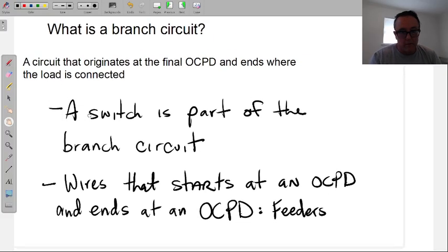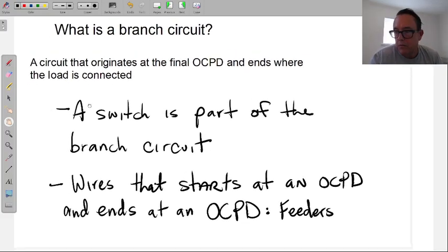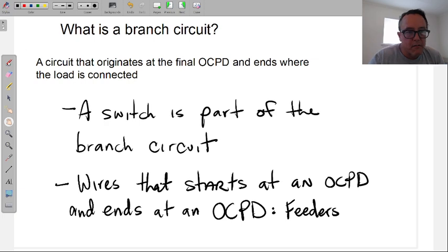So if ever you get thrown into a warehouse with a bunch of different machines and things that you haven't seen before, and you're trying to figure out conductor size, there is a whole rule set to sizing wires for branch circuits and sizing wires for feeders. This is one of the major reasons why these two things get separated. Because at the end of the day, there's just wires.